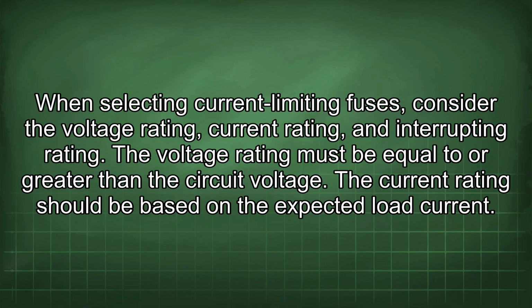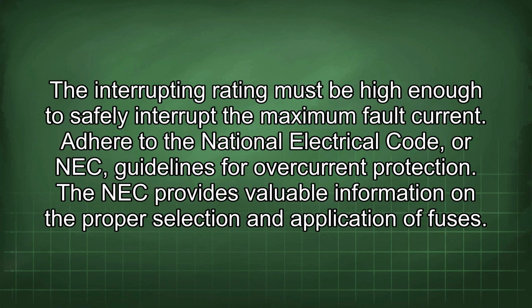When selecting current limiting fuses, consider the voltage rating, current rating, and interrupting rating. The voltage rating must be equal to or greater than the circuit voltage. The current rating should be based on the expected load current. The interrupting rating must be high enough to safely interrupt the maximum fault current. Adhere to the National Electrical Code, or NEC, guidelines for overcurrent protection. The NEC provides valuable information on the proper selection and application of fuses.